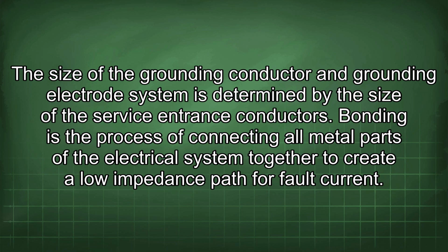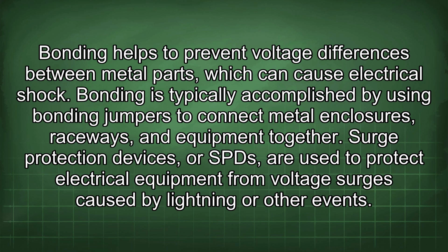The size of the grounding conductor and grounding electrode system is determined by the size of the service entrance conductors. Bonding is the process of connecting all metal parts of the electrical system together to create a low impedance path for fault current. Bonding helps to prevent voltage differences between metal parts, which can cause electrical shock. Bonding is typically accomplished by using bonding jumpers to connect metal enclosures, raceways, and equipment together.